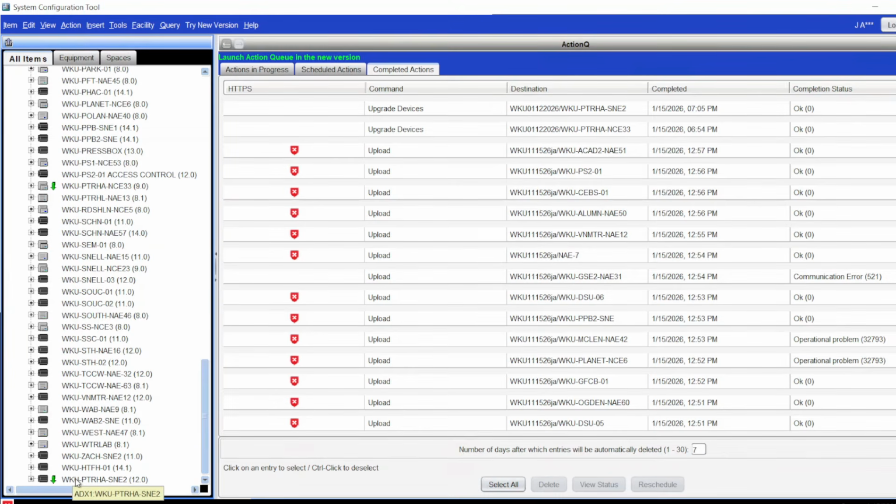But again, you need to make sure that you have that to match. And you can see down here with my mouse, it is version 12. Now, if I needed to go to version 15 or whatever, I can do that. But you can go forward, but you cannot go backwards. So again, I can't stress this enough. Quadruple check the version that is in the engine before you do this. Make sure that it matches.